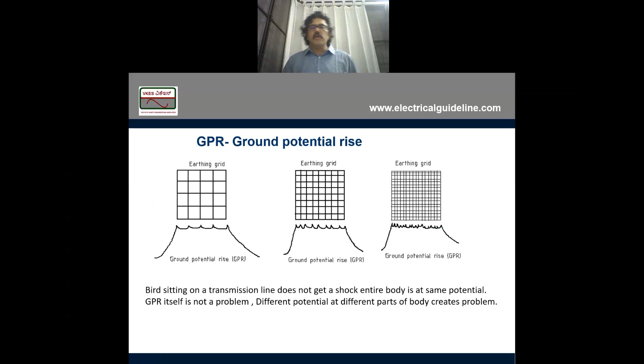Now, there's one more concept. Whenever there is a fault, only a part of the fault current causes the ground potential rise. Suppose the system fault current is 40 kA. You all know that. But for that particular substation, you have to find out the actual fault current. Let's say it comes around 25 kA or 20 kA. When you are doing the substation earthing design, you have to find out what fault current flows through the earth. It is only that current flowing through the earth which actually causes the ground potential rise, not all of it.